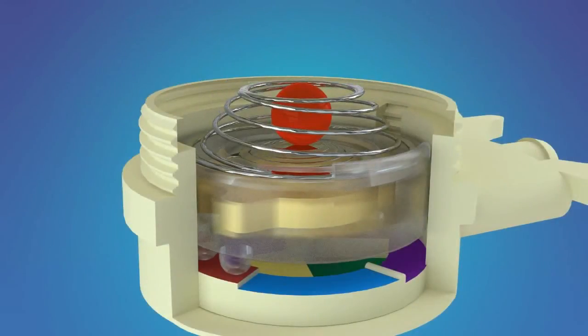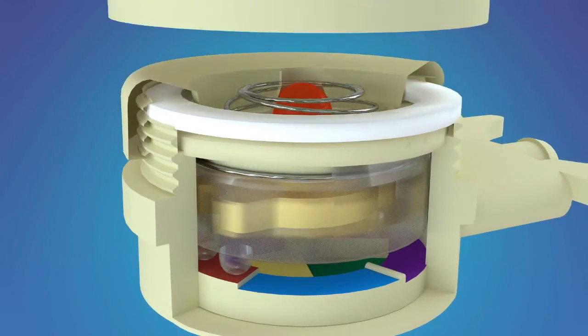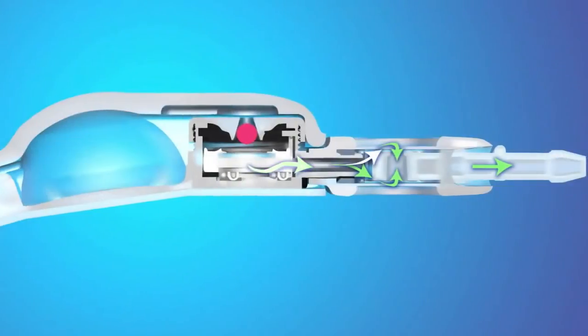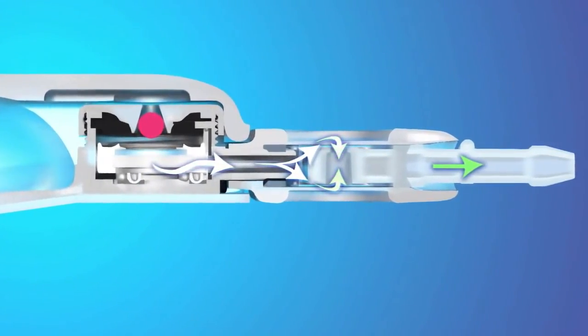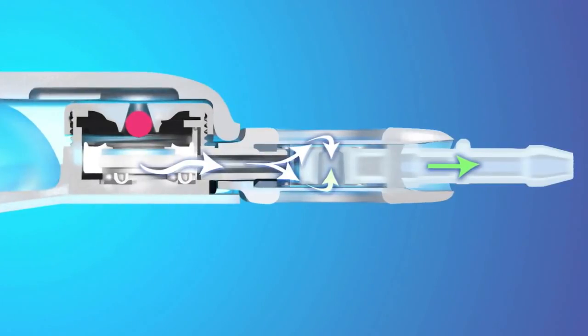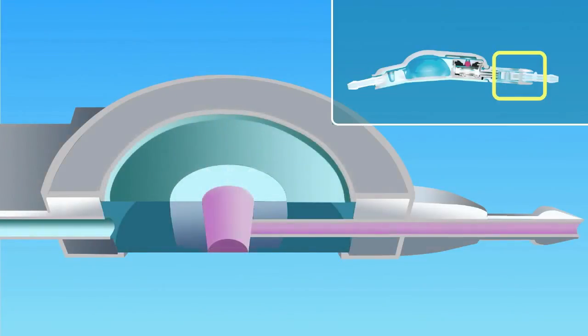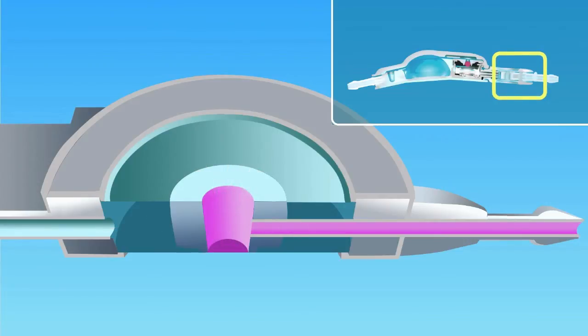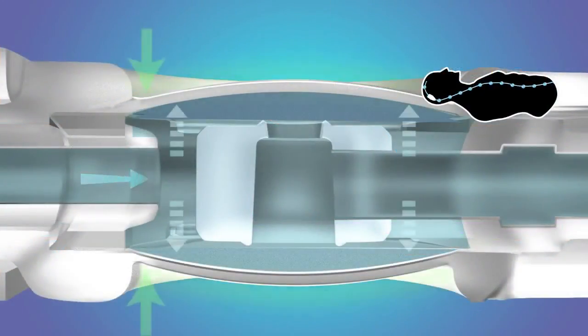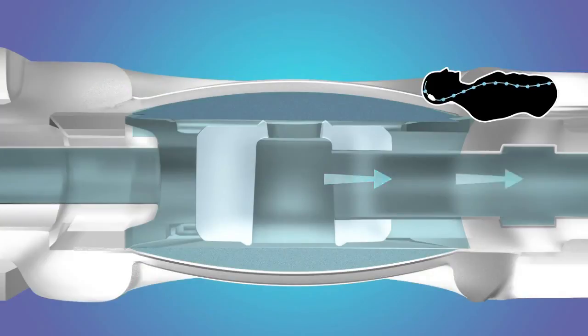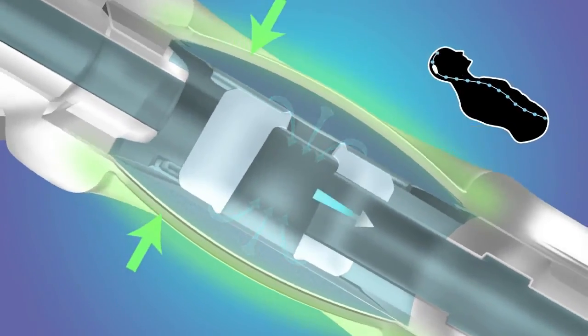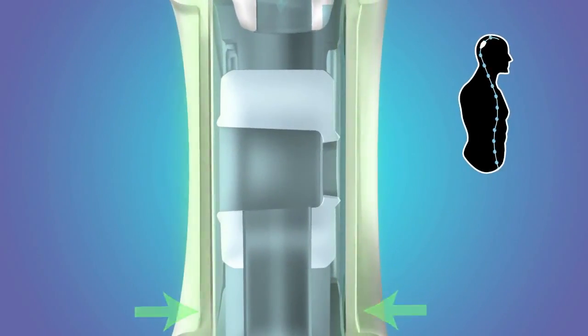The rotor retention spring helps to stabilize the magnetic rotor on the selected valve setting. Once the CSF passes through the adjustable valve mechanism, it enters the delta chamber. As discussed with the delta valve, the inlet diaphragm area is greater in size than the outlet port area, thus allowing the positive inlet pressure to control the delta chamber while minimizing the effects of the negative hydrostatic outlet pressure. When the patient is in the supine position, the membranes on either side of the delta chamber are relaxed or open, allowing for CSF flow. When the patient stands up, the negative pressure pulls the membranes closed, reducing the flow of CSF.